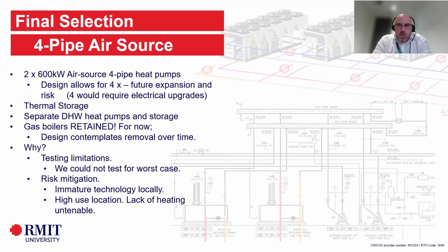We looked at four, which would exactly correlate with the existing boiler capacity. There was some concern that if we reduce that, there would be an elevated risk. And the reason we went with 2 in the first instance: we've designed the system to accommodate 4 overall in the event that it's needed, but 4 would have required an electrical upgrade. And based on the loads that we've seen, 2 will be sufficient, and that peak can be trimmed with some design modifications. So as an example, start the building a little bit earlier on those peak days.